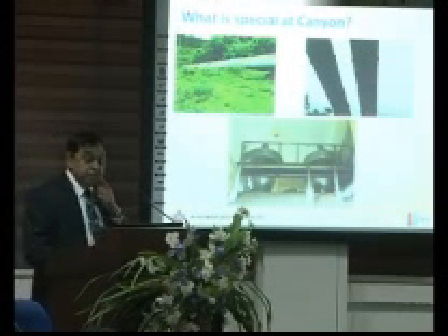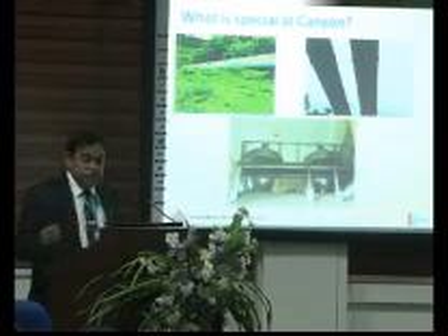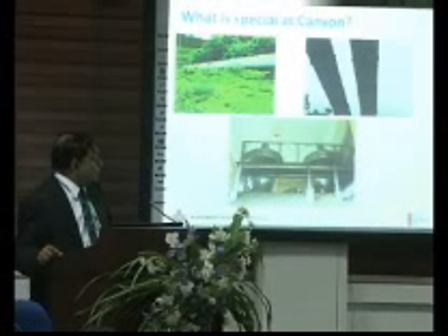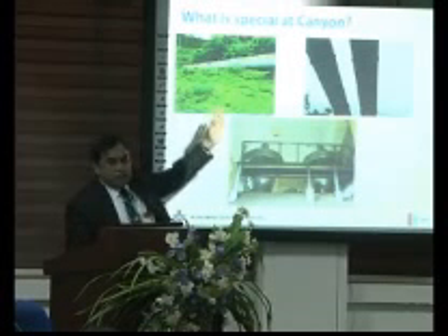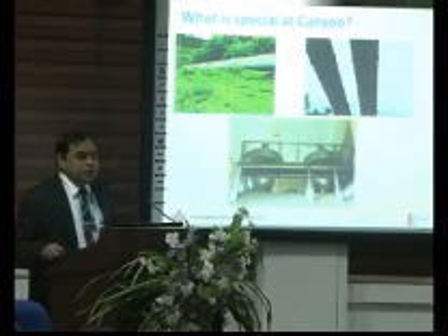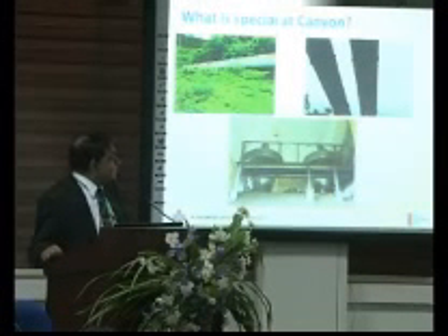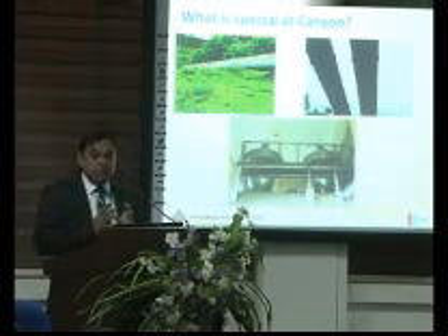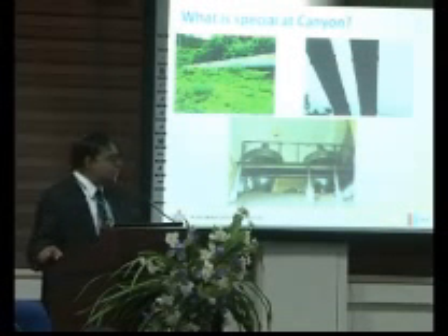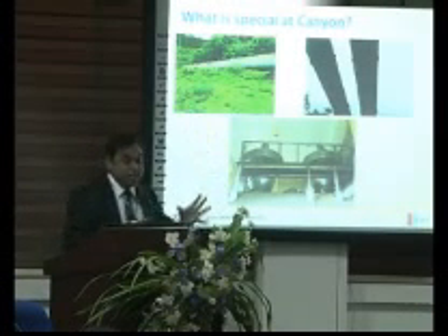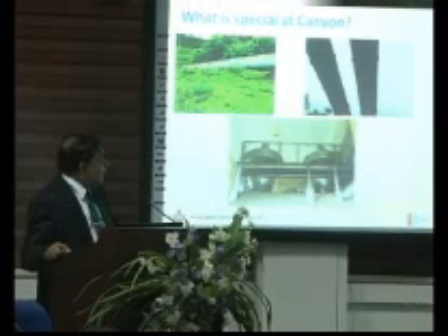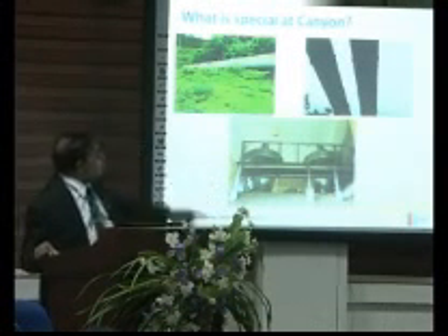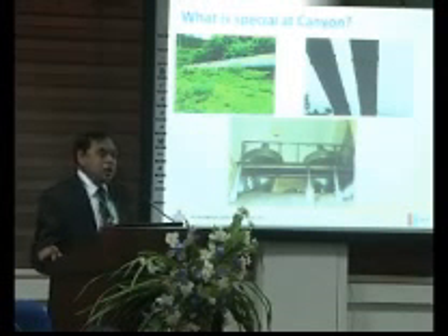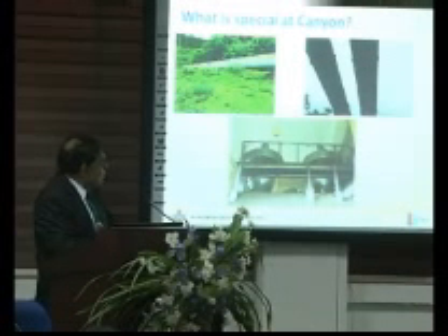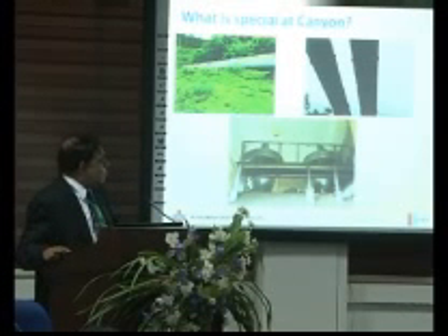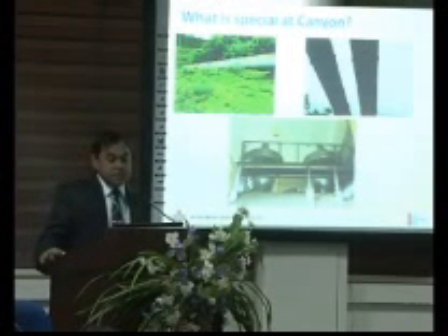And actually, there is another thing that happens when the discharge is heavy. The head losses are so large that sometimes a vacuum is created in the top part of this tube. Hydropower plants have a mechanism to safeguard against such a vacuum, because these tubes can take pressure from inside, but they are not designed to take pressure from outside. If a vacuum is created, these thick penstocks tend to distort. So, to avoid that, we have anti-vacuum valves. 2 of them are positioned here, and if a vacuum is created, these valves open and safeguard the plant. And this has happened once in Canyon Power Plant. Due to that, that is one more reason not to take 60 megawatts.